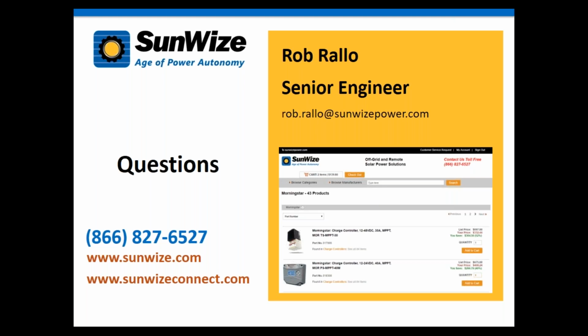Rob: I think there are actually two things here. First, yes, this is all with regard to non-hazardous locations. If you install these in a hazardous location, you may need to use a certified enclosure, and the system probably needs to be certified—there's a whole lot of other rules and regulations associated with that. The other thing is I think what this person is addressing is whether there's a risk of these components igniting the gas in the batteries.